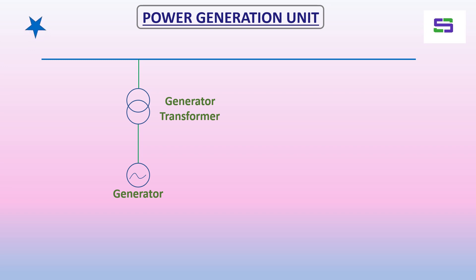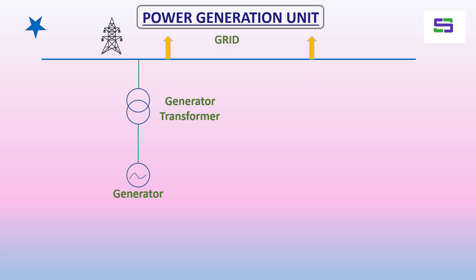So the generator transformer is required, and there is a switchyard — you can say outdoor substation or switchyard — at 400 kV, 132 kV, 220 kV, or 765 kV. This switchyard is connected further towards the grid for power evacuation. The generator generates power, it is stepped up, and connected with the switchyard to link with the grid. This is the upstream network.